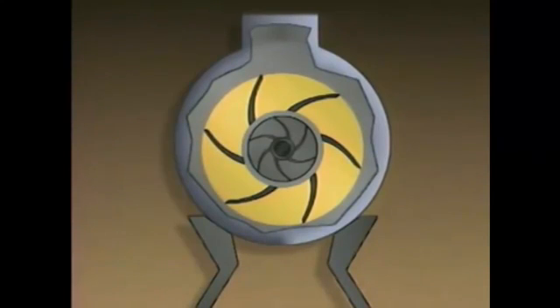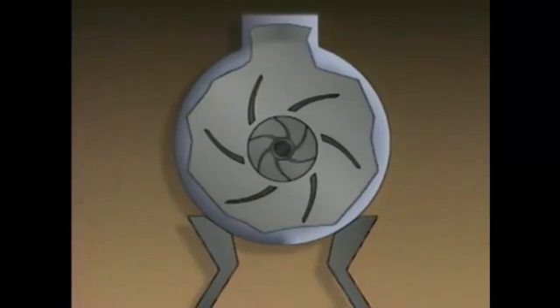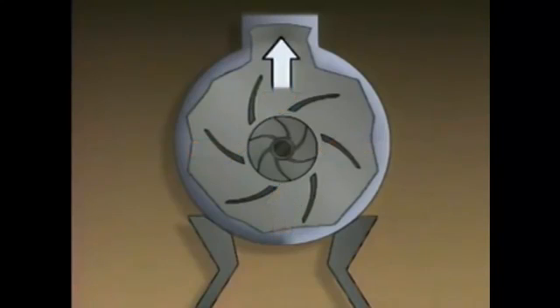As the gas leaves the impeller and flows between the diffuser vanes, the gas slows down and its velocity is converted into pressure. The series of small volutes helps minimize radial thrust by equalizing the pressure around the impeller. The pressurized gas is then directed into the discharge line. In general, single-stage centrifugal compressors produce fairly high gas flow rates, but their discharge pressures are relatively low.